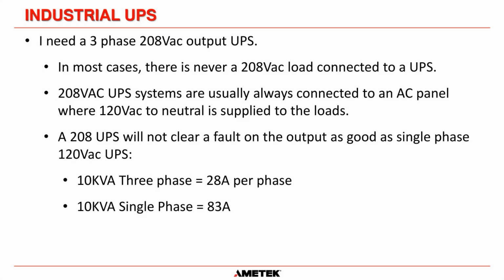And the first thing is, for an industrial UPS, most people say, well, I need a three-phase 208 volts output UPS. Now, in most cases, not in all cases, but in most cases, there is never a 208 volt load connected to a UPS, okay? It is usually always a 120 volt system. The 208 will go into an AC panel, and those AC panels will be split to 120 volts to neutral supplies that then go out to the loads, okay?